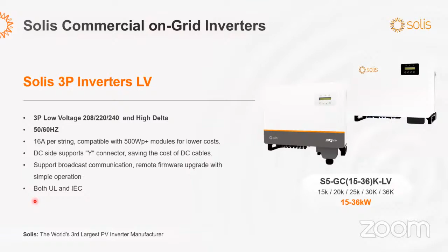And then we go to one of our most popular inverter models for Latin America, the 50 to 75 kilowatt inverter, low voltage. So we continue with the same line of compatibility with low voltage configurations and a high delta. All of these inverters are pretty much plug and play under these configurations and requirements, and they all come with the grid standards for Latin America. And if we need to adjust those parameters, it's very easy directly on the display.